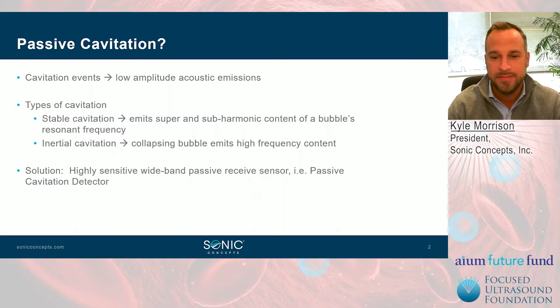So here's a general illustration of an ultrasound transducer emitting sound to an intended focal site. And there's a PCD receiver that's transverse, looking in perpendicular. And so here's a PCD, and the PCD often needs filtering, which we're using notch filters to dampen out the transmit fundamental and harmonic frequency content of that focused ultrasound transducer. And then the line goes into an oscilloscope where you detect the waveform, provide an FFT to get the amplitude and frequency content of those events.